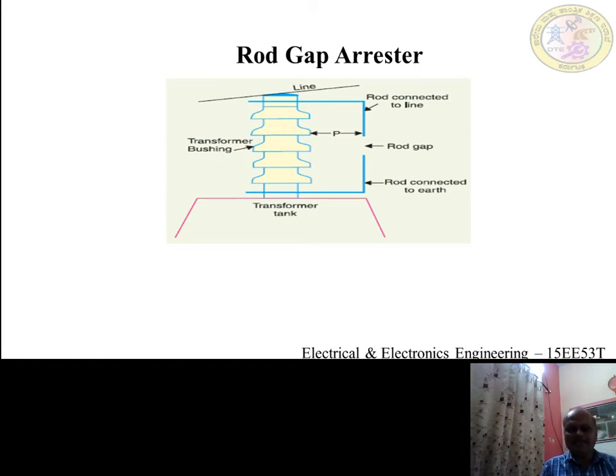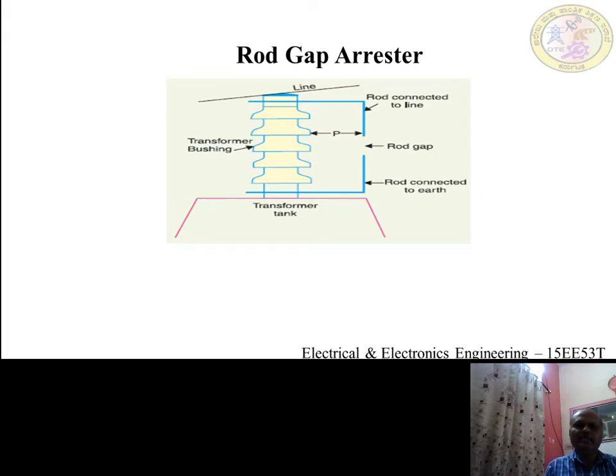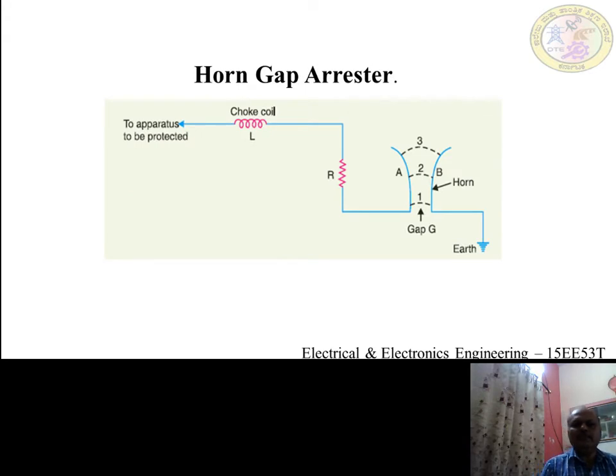The first one is the rod gap arrestor. Looking at the diagram, there are two rods made up of iron, with the length of each rod being 1.5 centimeters, bent in the form of a right angle. There is a gap between these two rods. One end of the rod is connected to the line and the other rod is properly grounded. Generally, the gap length is so adjusted that breakdown should occur at 80% of spark-over voltages. Under normal operating conditions, the gap remains inoperative. On the occurrence of a high voltage surge on the line, the gap sparks over and the surge current is conducted to the earth.